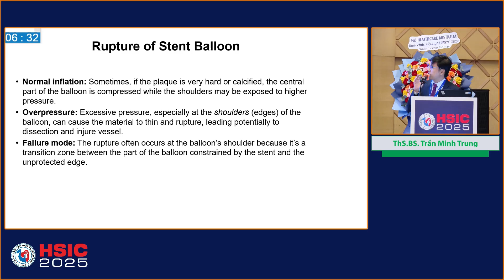If we overpressure, like in my case, we did 18 atmospheres, which is the rated burst pressure. If we have excessive pressure, especially at the shoulder, the edges of the balloon, it can cause the material to thin and rupture. It can potentially lead to dissection and injure the vessel. In my case, the rupture can occur at the balloon shoulder because it is the transition zone between the part of the balloon constrained by the stent and the unprotected edge. This is the mechanism of balloon rupture: when we overinflate the balloon with excessive pressure, it can lead to rupture at the edge of the balloon.